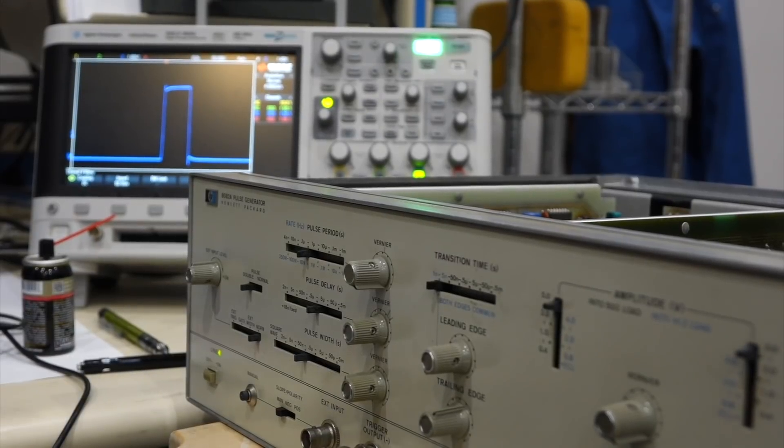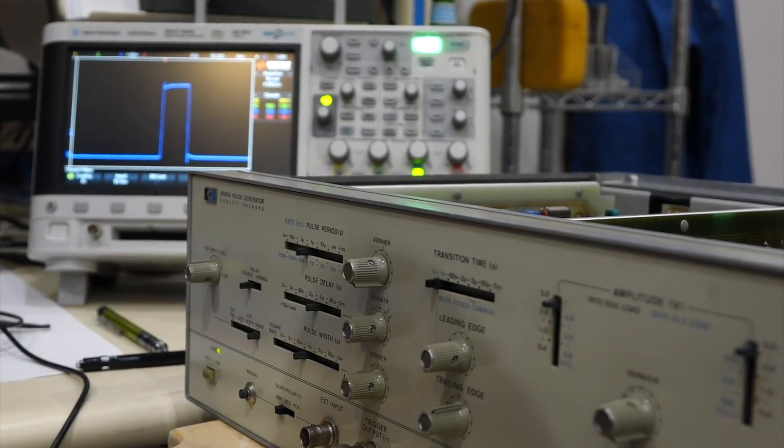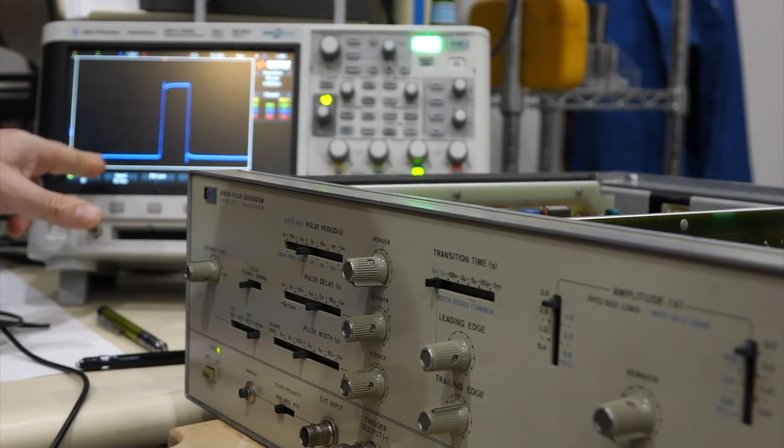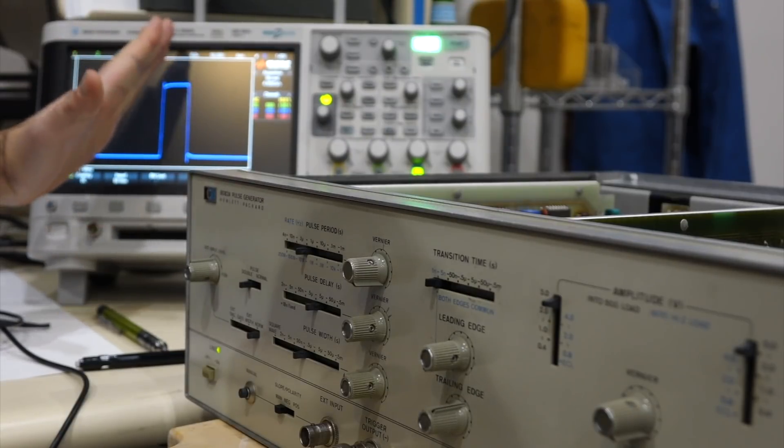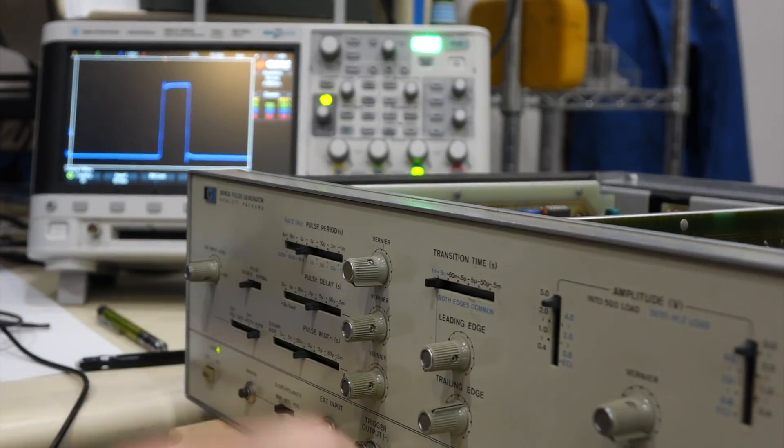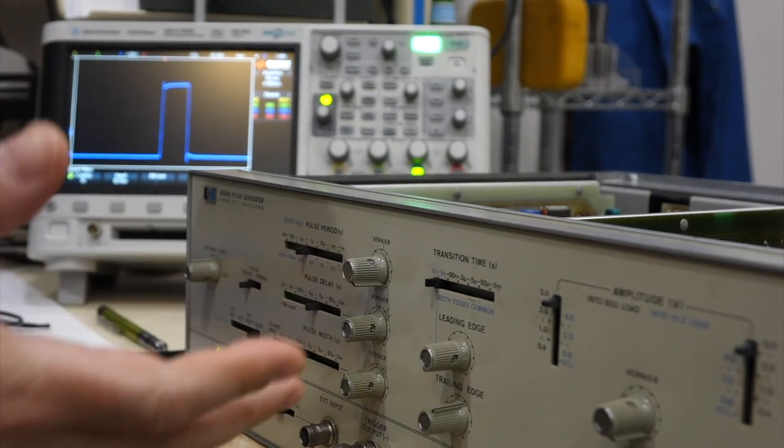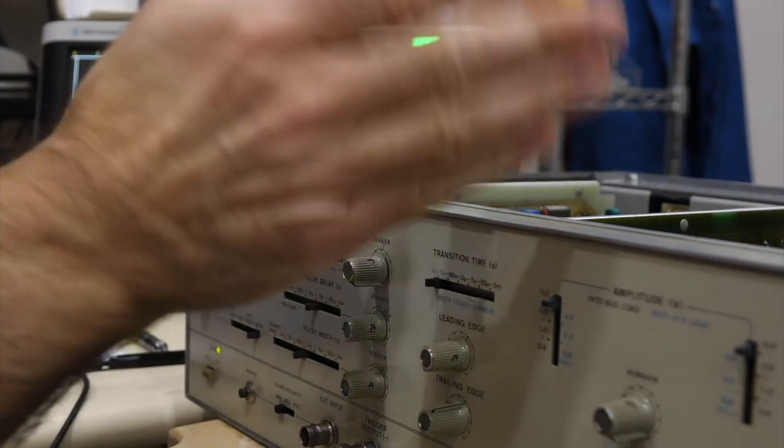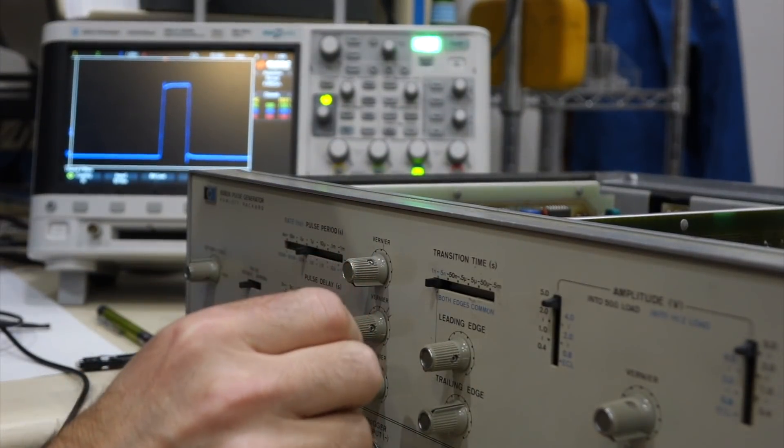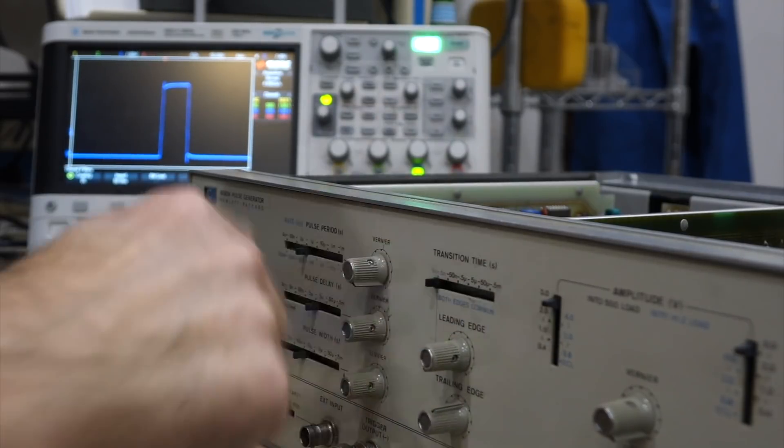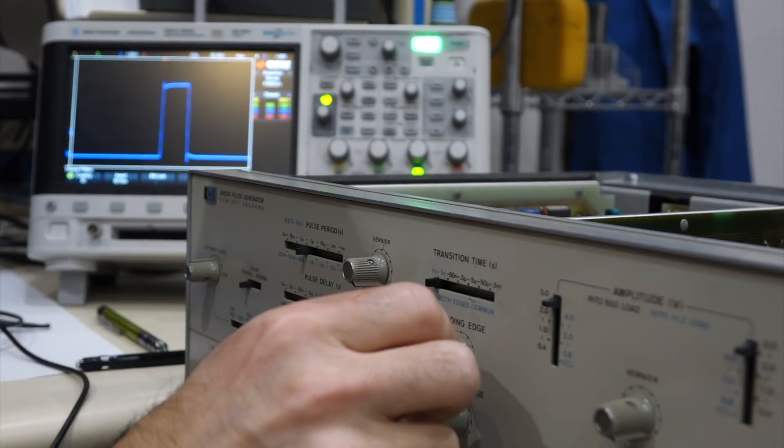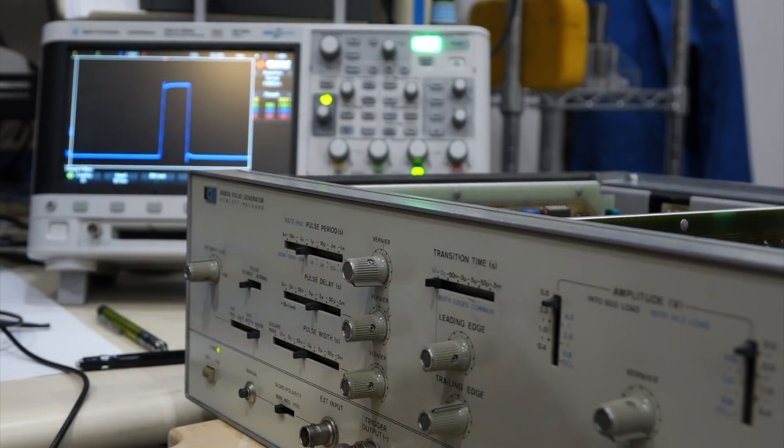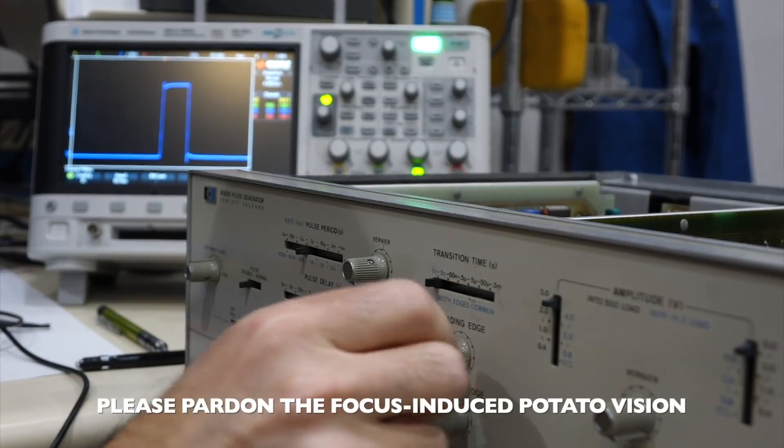Before I spend more time on this machine to make a replacement circuit for my failed IC, I wanted to see if I could do something about the other problem, which is the rise time control, which wasn't working all the time. And is probably the most important feature of this instrument. And it takes almost half the machine to make this thing happen. And I adjusted the whole thing, and it's better. It was very much out of adjustment, I think, to compensate for the fault.